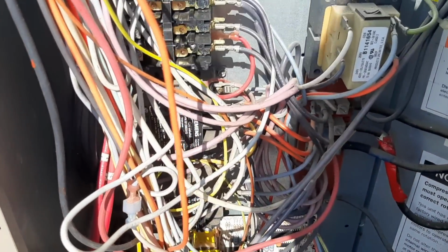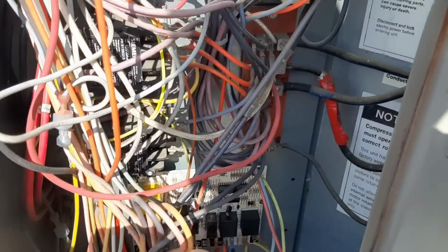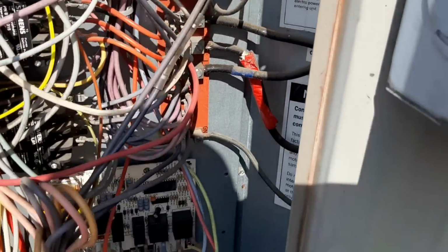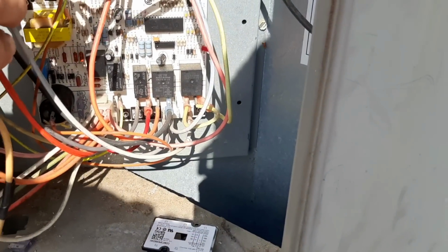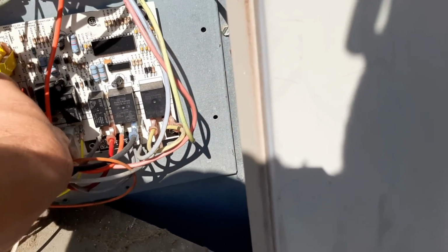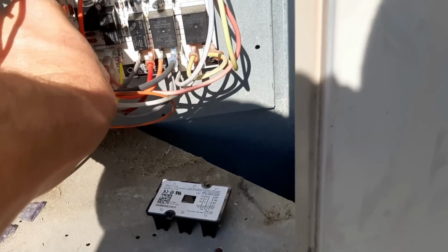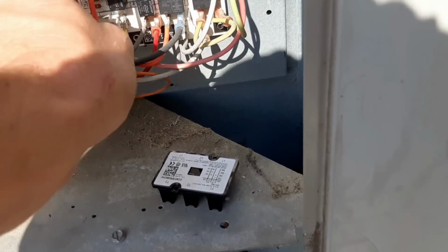This ought to be fun. That contactor's been replaced. Low voltage fuse isn't tripped, so I'm guessing we tripped a breaker and maybe we've lost a compressor. I do have a fuse on the board here that I can't see.